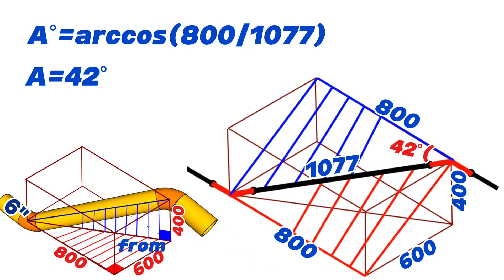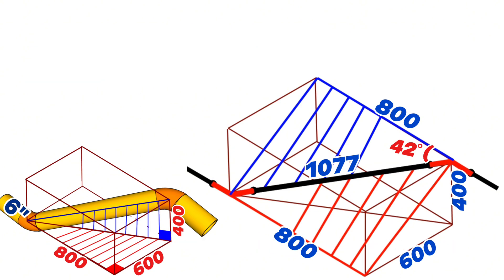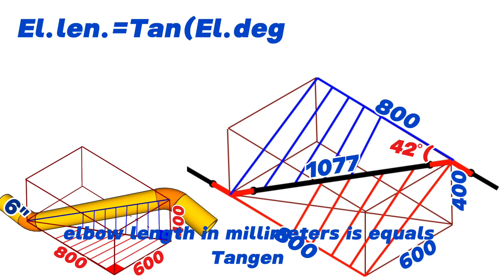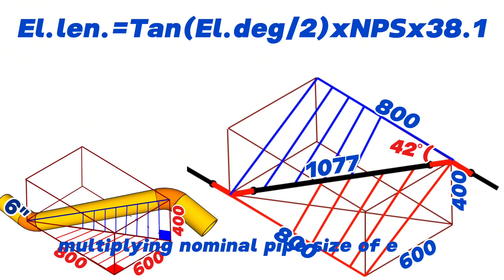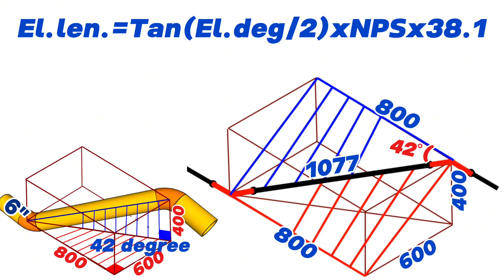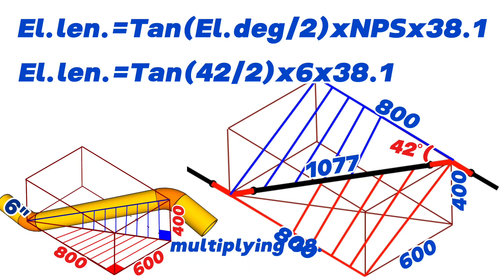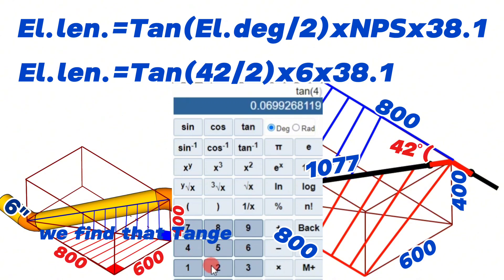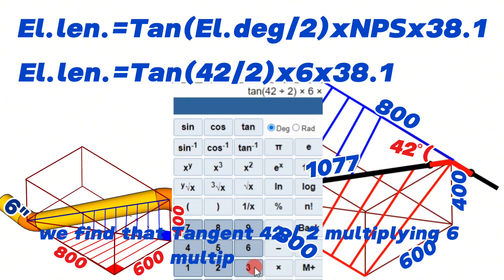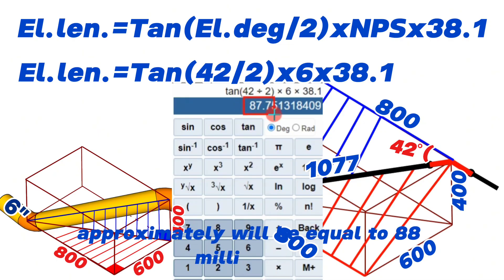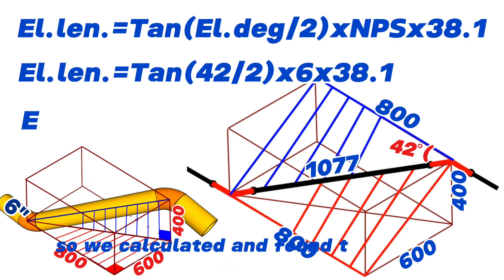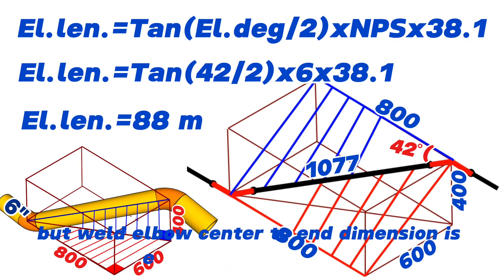Now let's calculate the center-to-end dimension of the cut elbows. The formula is: elbow length in millimeters equals tangent of (elbow degree divided by 2), multiplied by the nominal pipe size (NPS), multiplied by 38.1. For a 6-inch 42-degree butt-weld elbow: center-to-end dimension equals tangent(42/2) × 6 × 38.1. Using the scientific calculator, this equals approximately 88 millimeters. So the 6-inch 42-degree butt-weld elbow center-to-end dimension is 88mm.